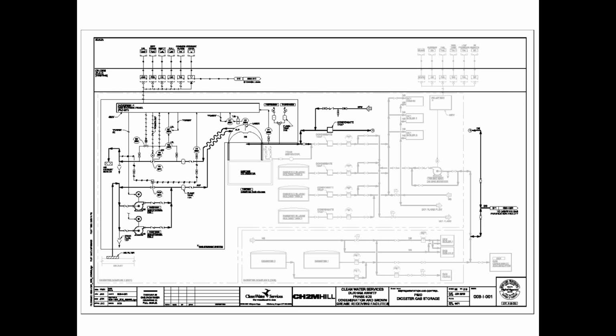One thing I wanted to point out is that in some instances the line or pipe may not be fully drawn out. Up in the upper right-hand corner of the large window, where the dark line is, you'll see that the arrow ends with the number 1. If you trace that out directly across, you'll see that the 1 picks up there, and that tells you the line is continuous. They didn't draw the full line because it would have been in conflict with some of the other drawings they were trying to show you.